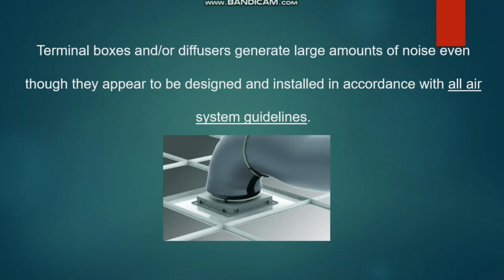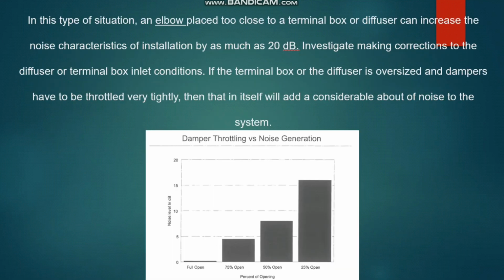And the next question is, terminal boxes or VAV boxes or diffusers generate a large amount of noise even though they appear to be designed and installed in accordance with all the air system guidelines. Generally, if noise is an issue, first, an elbow placed too close to the terminal box or diffuser can increase the noise level by as much as 20 decibels. This is an important case. We have to look for a nearby elbow or something near the VAV or the diffuser, so investigate making corrections to the diffuser or terminal box inlet.